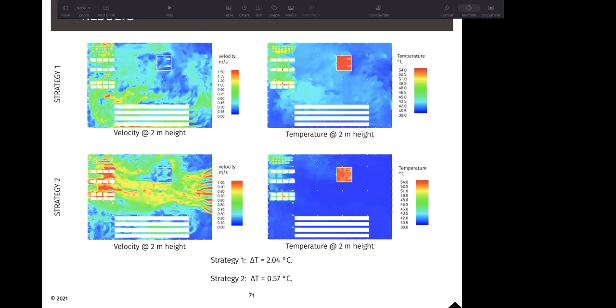Again, looking at both the strategies, we can see that for the first one, where the exhaust fans are mounted at the extreme end, the heat is carried from the equipment all through the factory and then exhausted at the right hand side of the factory. Whereas for strategy 2, because we have mounted the exhaust fans right above the equipment which is radiating heat, the heat is contained within that area, and there is minimum delta T, which is 0.57 degrees centigrade. In strategy 1, there is a delta T of 2 degrees up to human height.